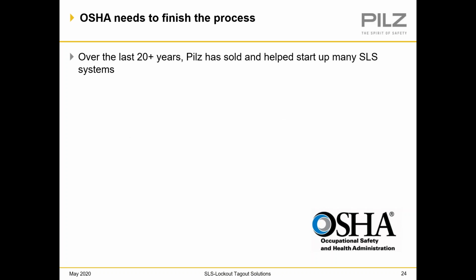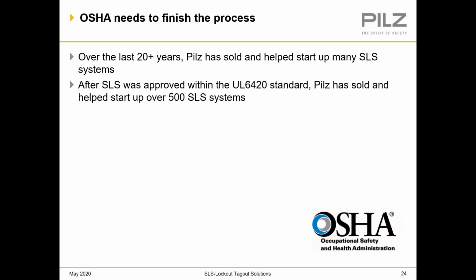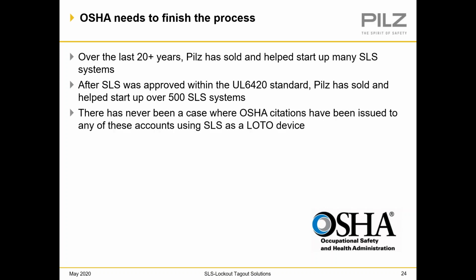So over the last 20 years, we have sold and helped start up many SLS systems. And when we got approval with the UL 6420 standard, we have also sold and helped start up over 500 SLS systems. So we have a very good track record with this solution. We've done it for many years. And as a matter of fact, there has never been a case where OSHA citations have been issued to any of these accounts using the SLS as a lockout device. So it's a great track record.